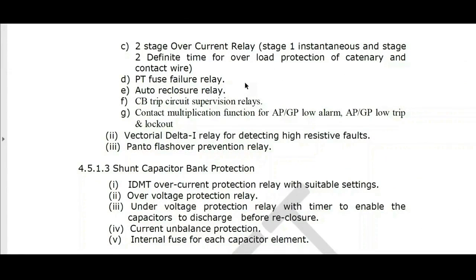If Z becomes 0, your measured impedance comes inside the drawing. Zm is less than Zs. And it will be treated like a fault. Whereas it is not a fault because only the fuse has failed. Therefore, the protection will be blocked whenever the PT fuses fail. Which protection will be blocked? Only distance protection will be blocked because that is only dependent on voltage. The overcurrent relay is actually not dependent on voltage. Therefore, it will be working as a backup. So this is called the PT fuse fail relay.